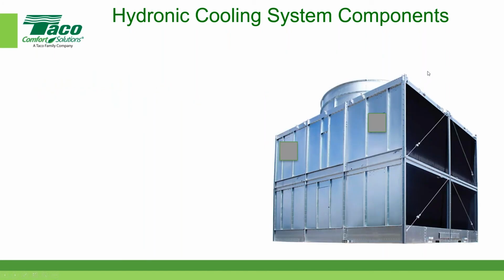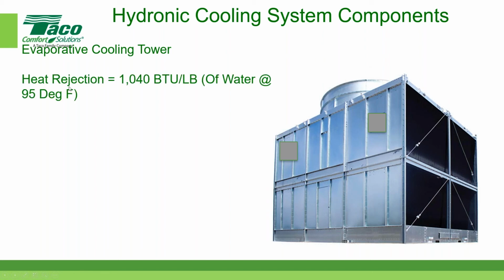So here's a picture of a cooling tower, and here are some interesting facts about cooling towers. It's called an evaporative cooling tower. They evaporate water to cool the condenser water. And cooling towers reject approximately 1,040 BTUs for every pound of water at 95 degrees Fahrenheit.